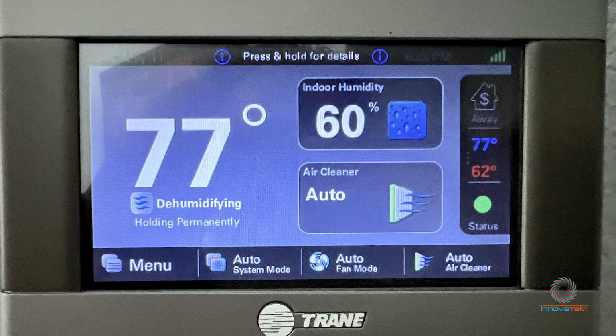So clearly this thermostat did not meet the humidity that was requested because it already reached the cooling temperature. This feature of overcooling allows you to tell the thermostat, in case you meet the set point of the temperature but the humidity has not gotten close to or met my set point of humidity, which in this case was 55, I allow you to overcool for an additional 3 degrees. You can set this from 0 to 3 degrees.